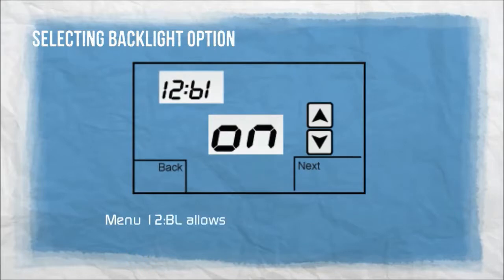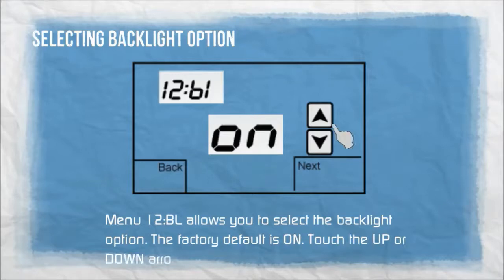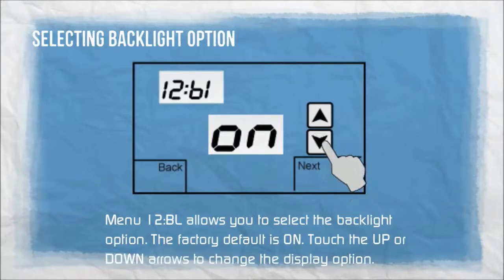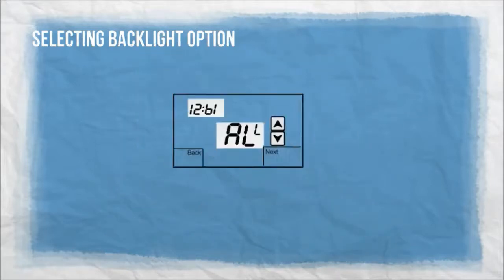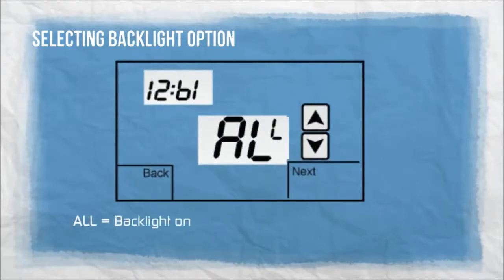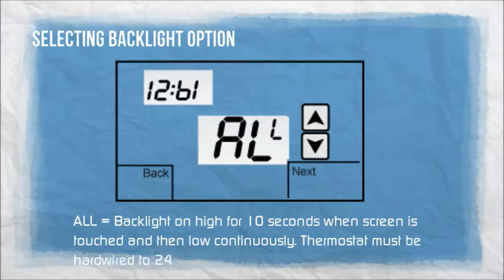Menu 12BL allows you to select the backlight option. The factory default is on. Touch the up or down arrows to change the display option. Off: no backlight. All: backlight on high for 10 seconds when screen is touched and then low continuously. The thermostat must be hardwired to 24VAC for this option.